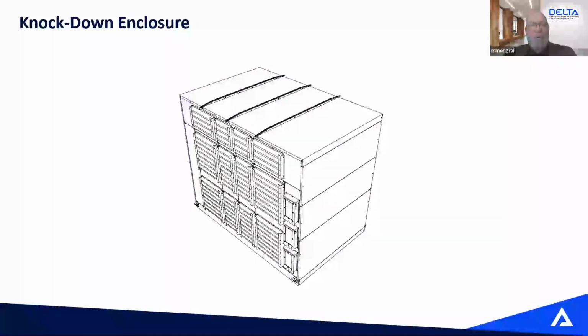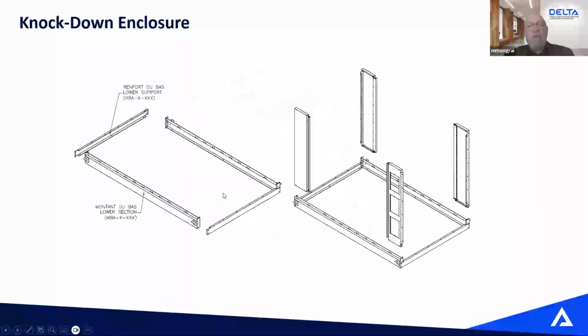At Delta, for our power transformers, we use what we call a knockdown enclosure design. So the fully assembled enclosure can be knocked down in pieces fairly easily, if I could say. Two men within 4 hours can bring down the enclosure to the smallest part possible. In most cases, when you deal with replacement, there's no way you can bring a fully assembled enclosure into the electrical room, but the way our enclosures are designed, it's pretty easy.